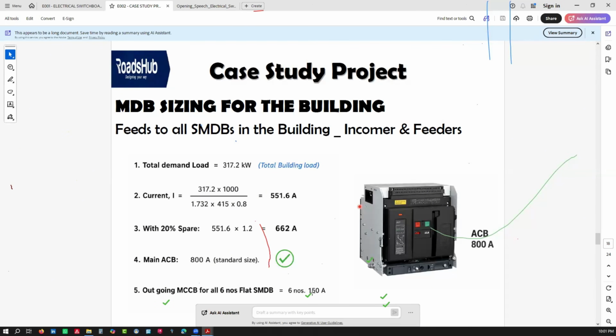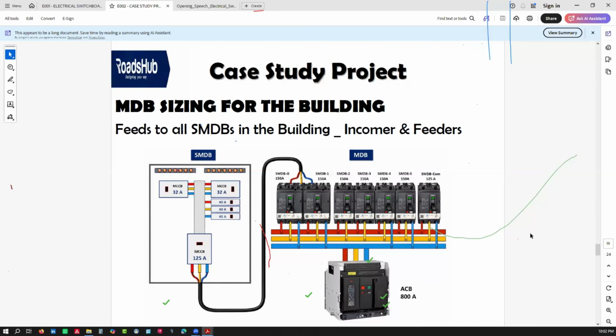But for domestic, you can actually just pick a breaker that has a higher value than the one inside the sub-distribution boards. You remember the sub-DB had 125, but for the MDB, and sometimes people use isolators in the sub-distribution boards because they know they have a tripping unit or a tripping breaker inside the main distribution board. So when you see those design permutations, it means if you don't put your brain into it, you might design a wrong system. So what is the sample connection we are looking at for?